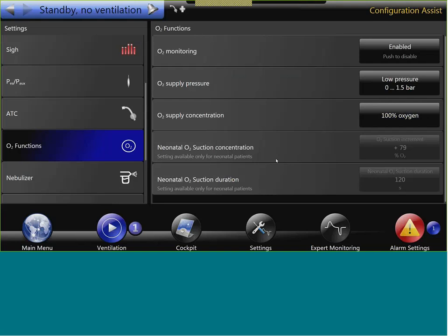Thanks, Anna. I just received the addition. How much FiO2 will be delivered maximum? That's depending on the oxygen concentrator. As the bellavista can't generate oxygen by himself, that's on the oxygen generator. So there are oxygen generators which generate 80 to 85%, some more, I think the highest ones are 94%. That's really up to the oxygen generator or concentrator.